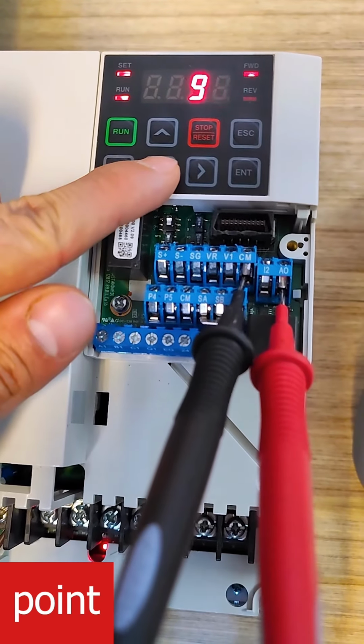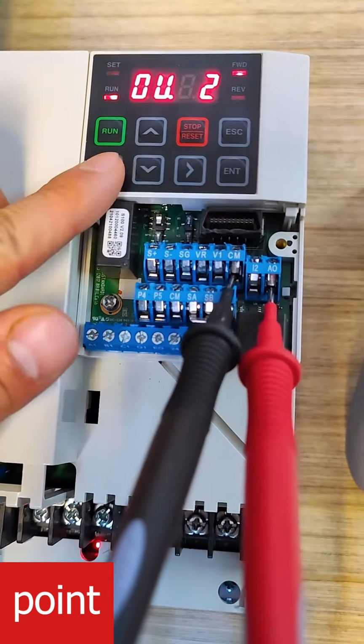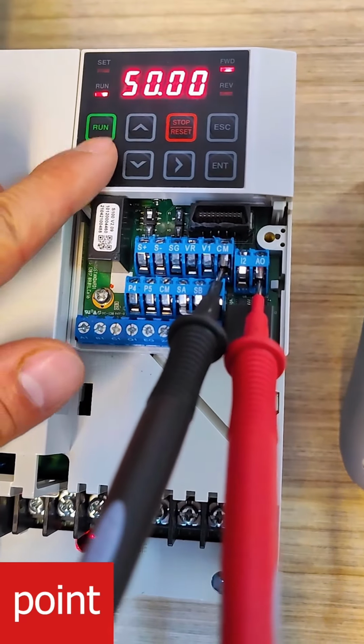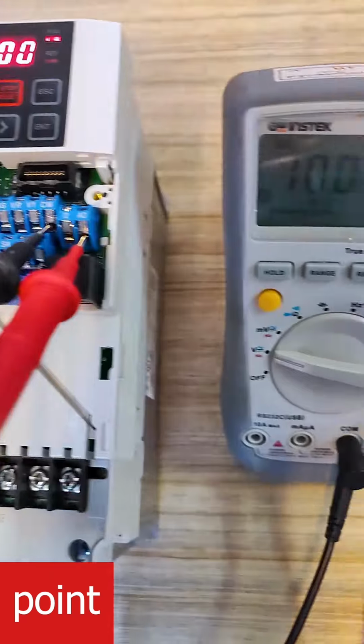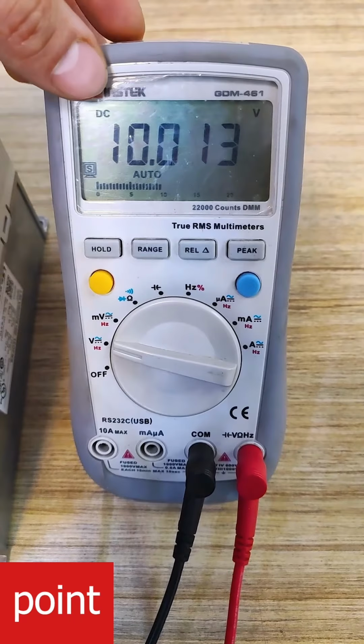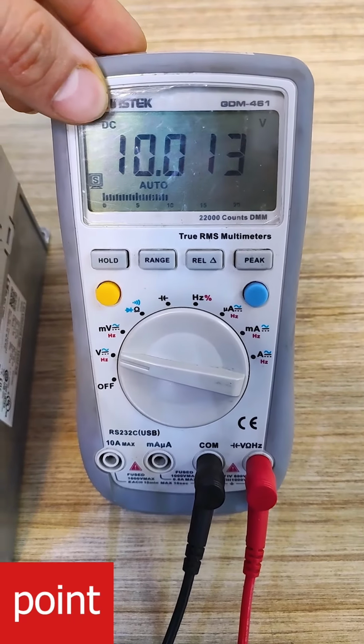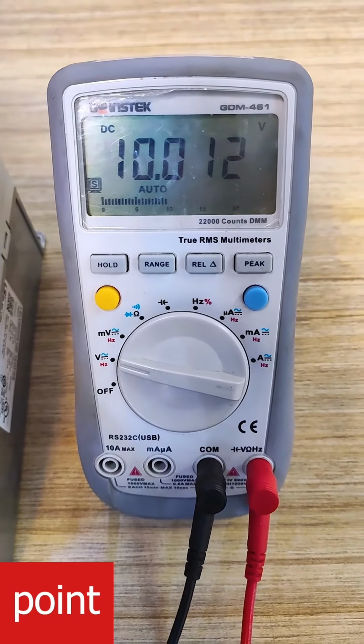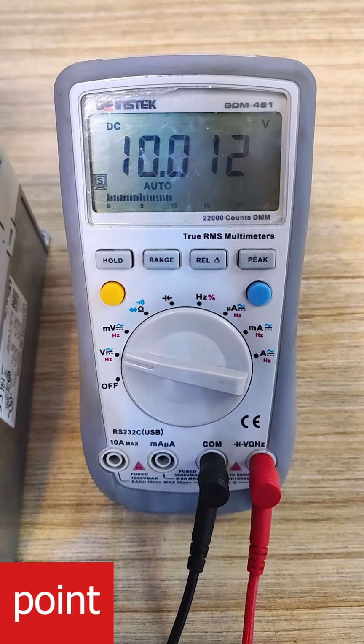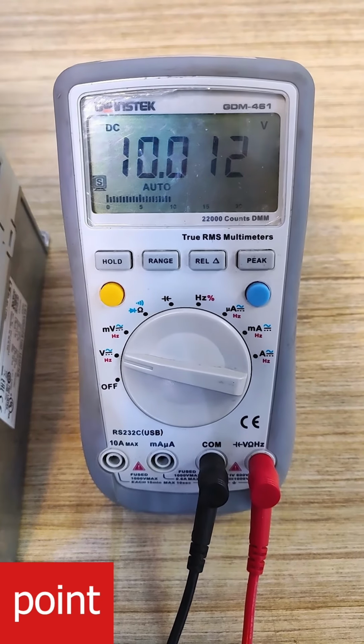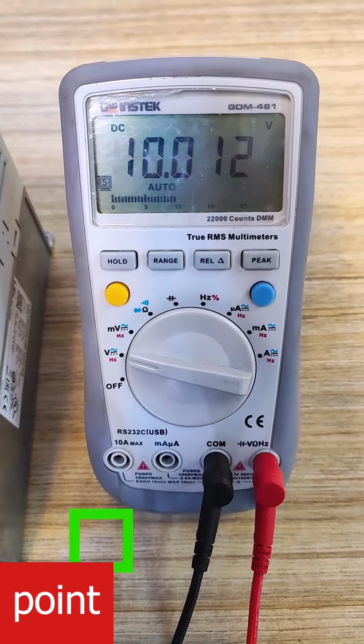For example, if I set this to 97% and go back while the inverter is running, if you look at the voltmeter, you'll see that my analog output is now 10 volts. So if your voltage is a bit higher or lower, you can use parameter OU02, which is related to the gain, to adjust your scaling.